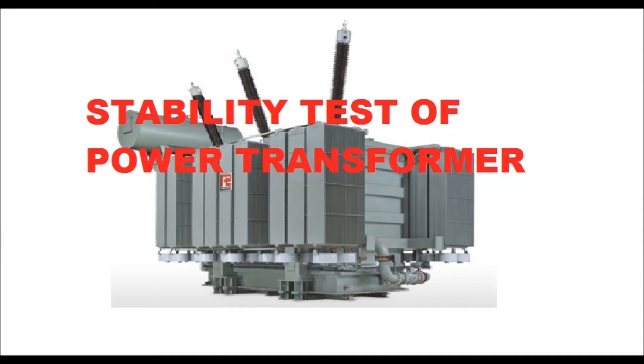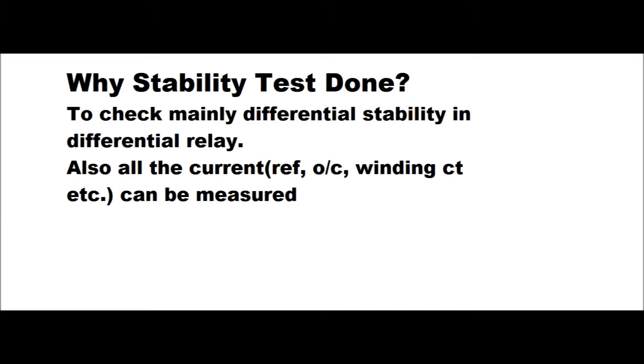In this video we will discuss the stability test of a 50 MVA 132/33 kV YNd1 vector group power transformer. The stability test is done after all other tests, mainly to check the differential stability — the differential current (id) must be zero for all phases. Also, currents for the REF relay, backup overcurrent for HV and LV winding, HV WTI and LV WTI CT secondaries are measured. This is the final test before charging clearance is given.